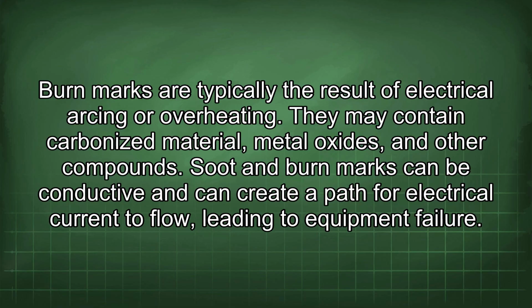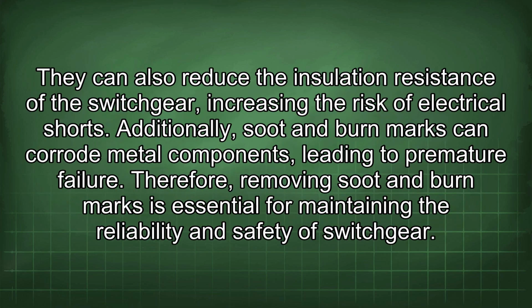Soot and burn marks can be conductive and can create a path for electrical current to flow, leading to equipment failure. They can also reduce the insulation resistance of the switchgear, increasing the risk of electrical shorts. Additionally, soot and burn marks can corrode metal components, leading to premature failure. Therefore, removing soot and burn marks is essential for maintaining the reliability and safety of switchgear.